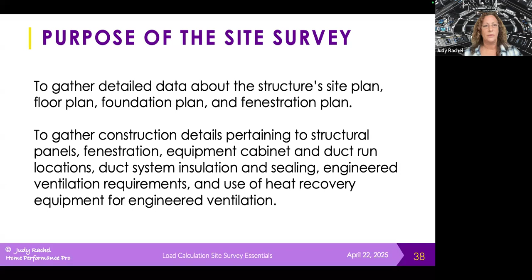The purpose of what is called the site survey is that there is a lot of data and a lot of details that we need to collect about the structure and where it is in order to do our load calculation. So we've got to gather all the construction details pertaining to the structure: the walls, the fenestrations, and then even there are loads from equipment and from ducts, the location of the ducts, how well the ducts are insulated, and if there's any whole house ventilation. That also is going to affect our load calculation, as well as infiltration. So we've got a lot of work to do in terms of getting all the data we need for a load calculation.